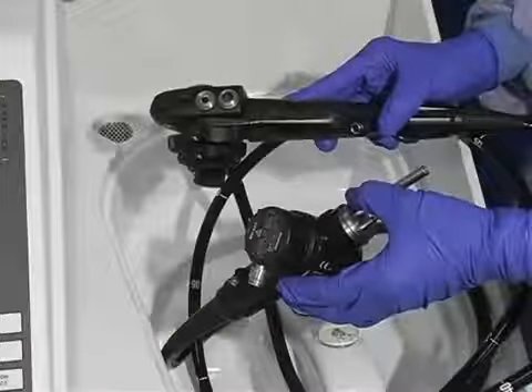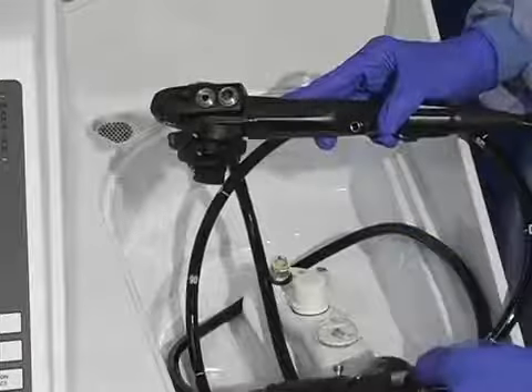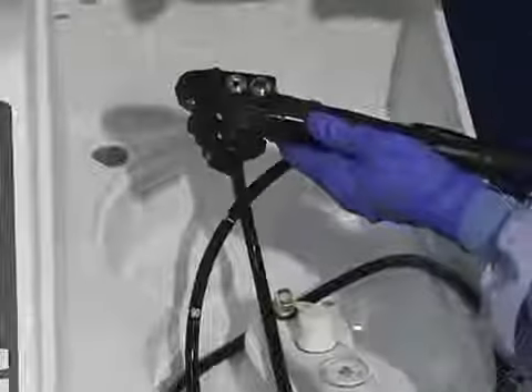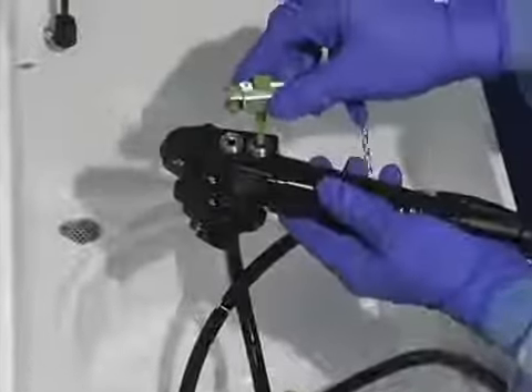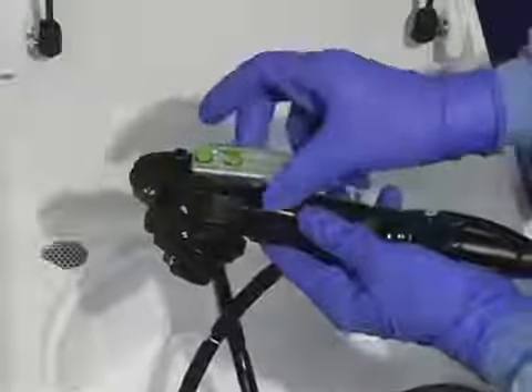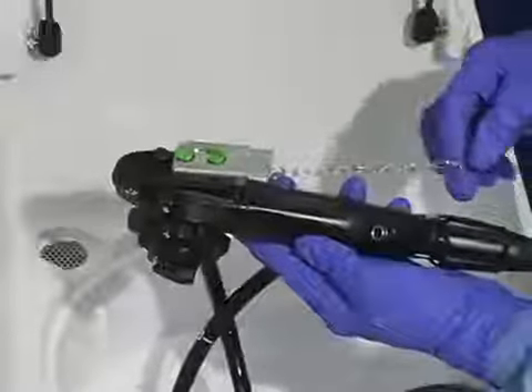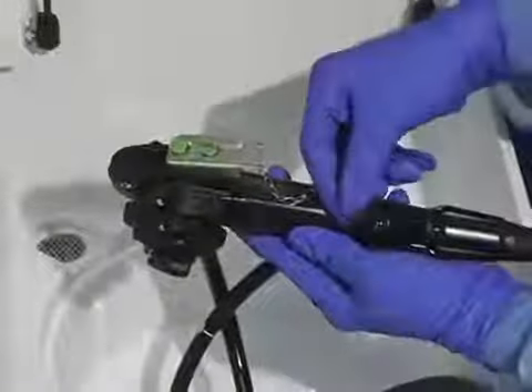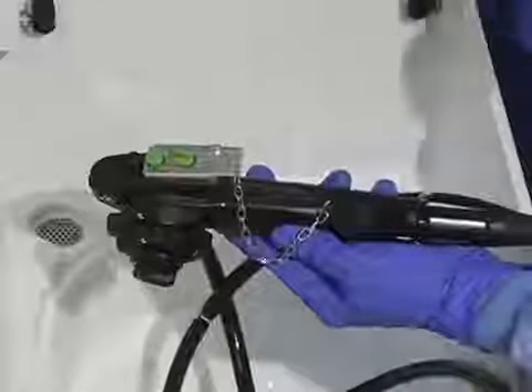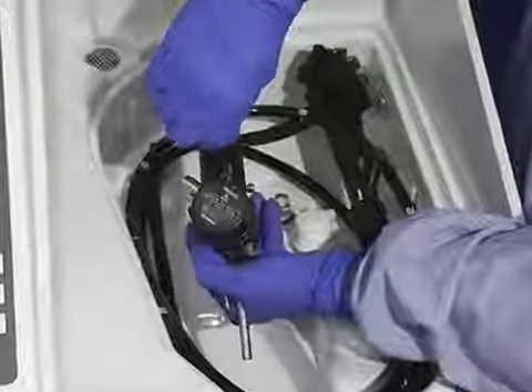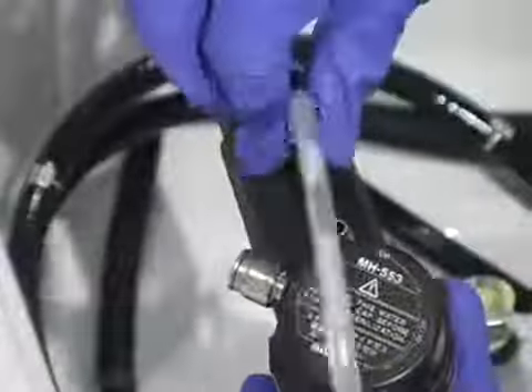The water-resistant cap should already have been attached and the valves removed during leakage testing. Attach the channel plug in the endoscope valve cylinders and attach caps onto the instrument channel port. Attach the forward water jet connector, gas and biopsy caps as needed.